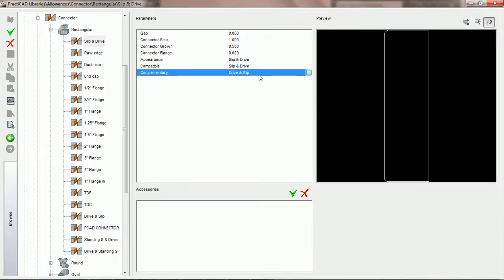The last parameter we have for rectangular connectors currently is the choice for complementary connectors. Now, complementary connectors is a very unique parameter which was designed specifically for connection types like slip and drive and slip. It is not used in connections like TDC, TDF, ductmate, and those where all four sides of the connection are identical. The reason why we're going to use slip and drive in this tutorial is because complementary connections help us to make sure that when we're attaching fittings in PractiCAD and rotating those fittings, we can get the specific side of a connection we want in the right place.